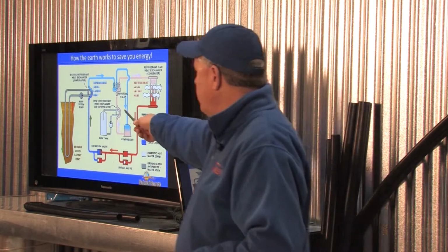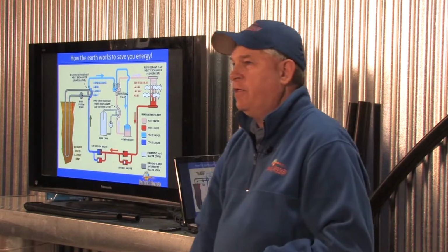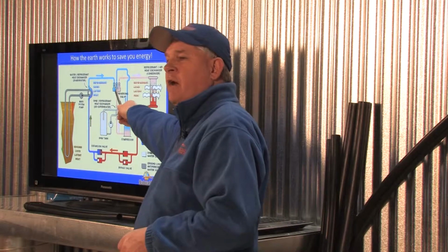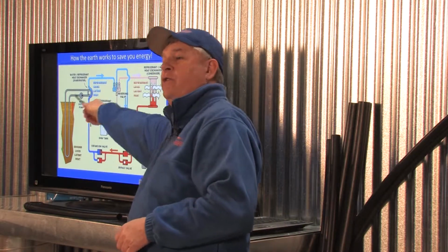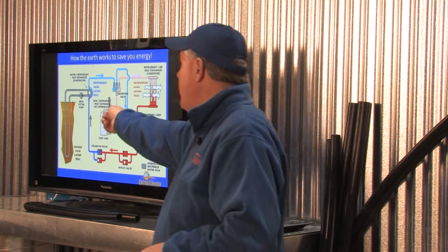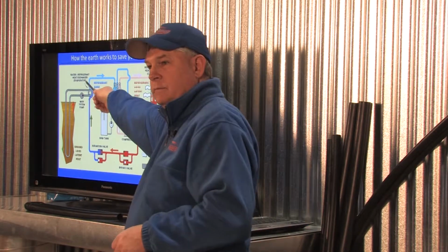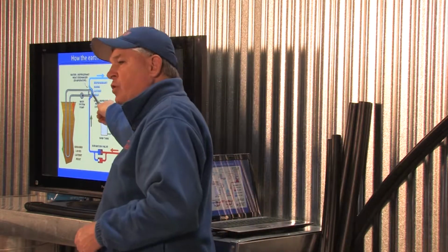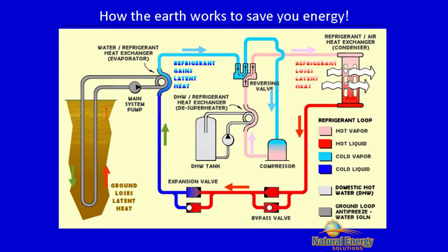Once we go past there, the only thing the thermostat did was tell this reversing valve, 'I want the heat to go that direction now.' Now my hot gas goes that way. So when it hits this earth loop, the refrigerant is the hot component. The earth loop didn't change, but it's the cooler component. It absorbs the heat, and the heat goes back into the earth. The refrigerant cools off.